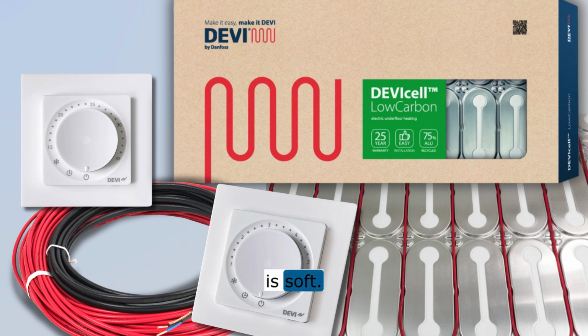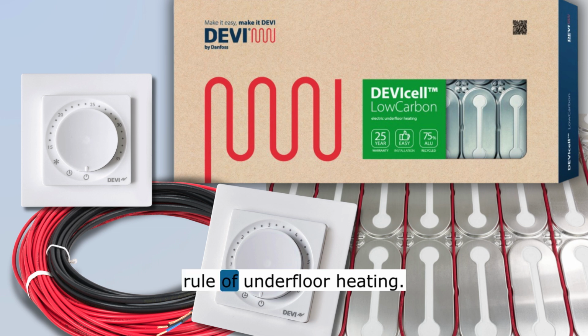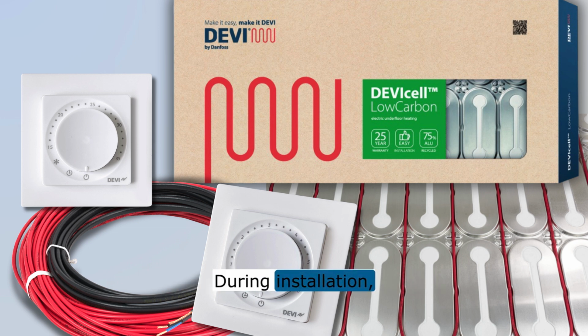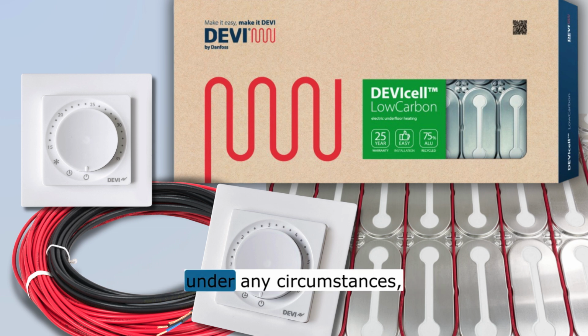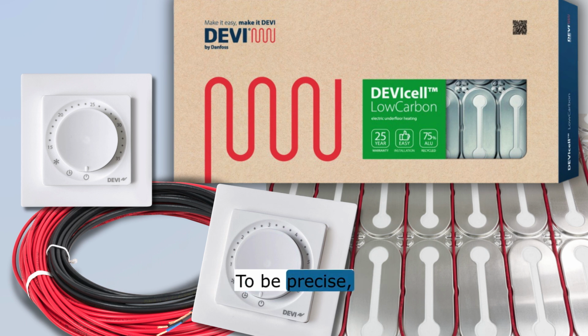Okay, so the cable is soft. You are laying it out. And here's where we hit the absolute golden rule of underfloor heating. The manual repeats this commandment multiple times. Yes, it does. During installation, you never, ever, under any circumstances, cut or shorten the heating cable. To be precise, you can cut the fiberglass mesh backing on a heating mat if you need to turn a corner, but you never take a pair of wire cutters to the actual colored heating wire.